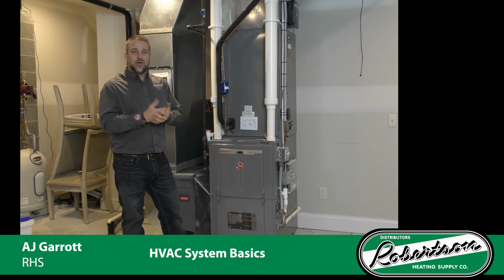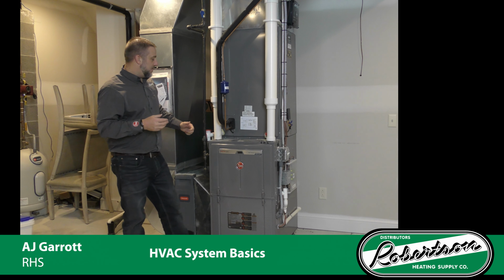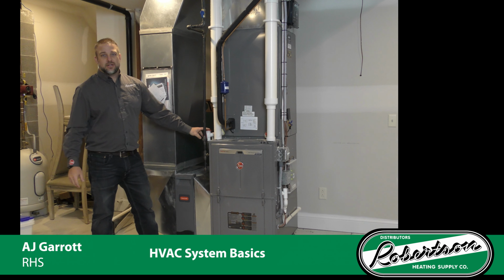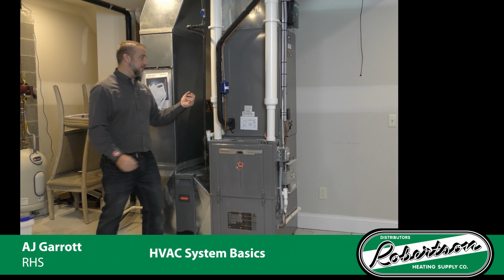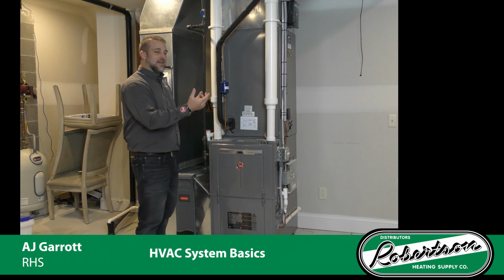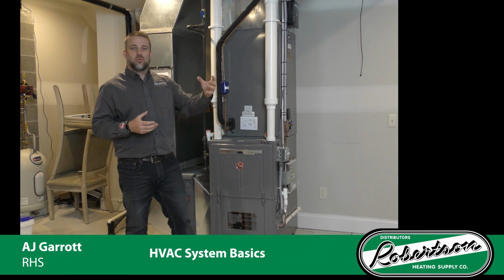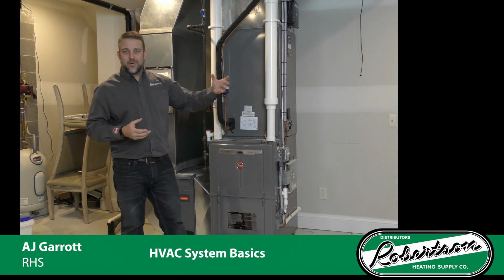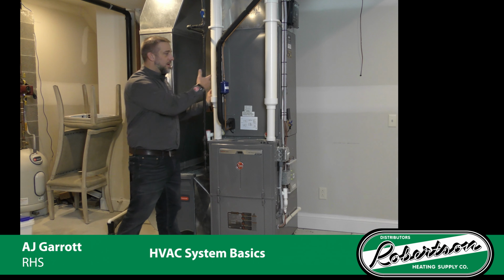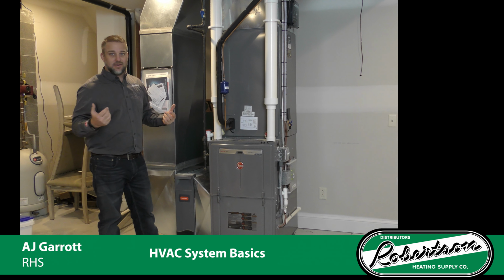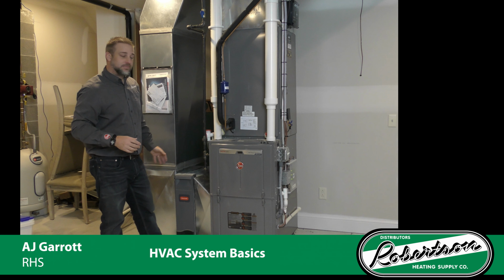We don't want any kind of moisture in with the refrigerant because it will not work properly if it is. We have to be able to drain an air conditioner. So on this side we have condensate coming out of the evaporator coil, because as we cool the air down, we actually take humidity out of the air and it begins to condensate. Much like a glass of ice water sitting outside in the middle of summer. You get condensate on the outside of that glass. We're doing the same exact thing going on here inside this evaporator coil. We need to get rid of that condensate. So we drain it out the corner here and it'll go down to a drain in the basement.